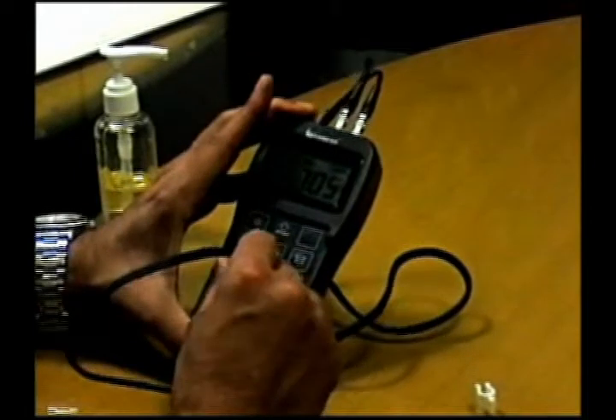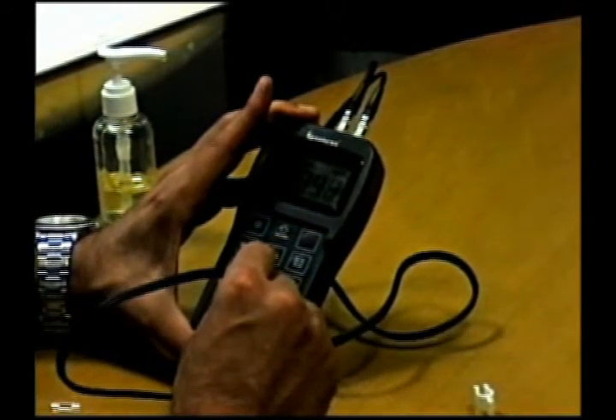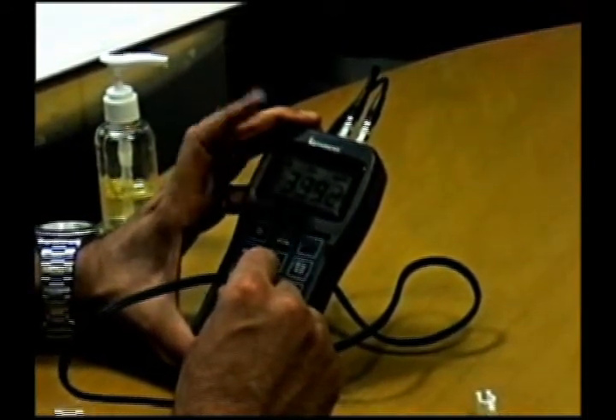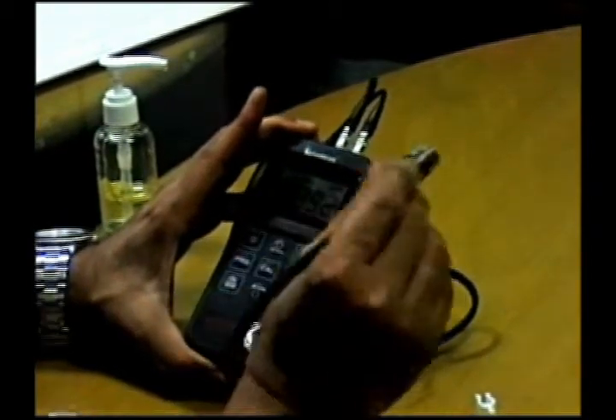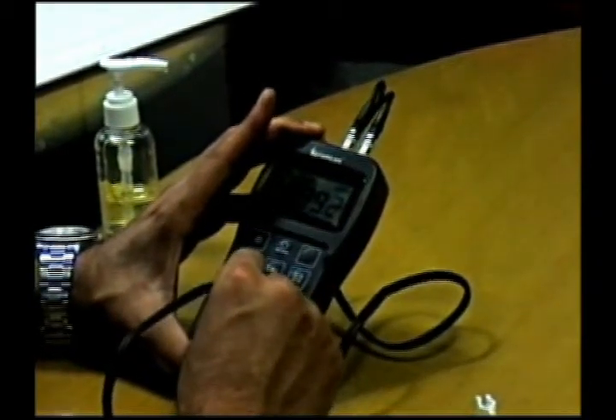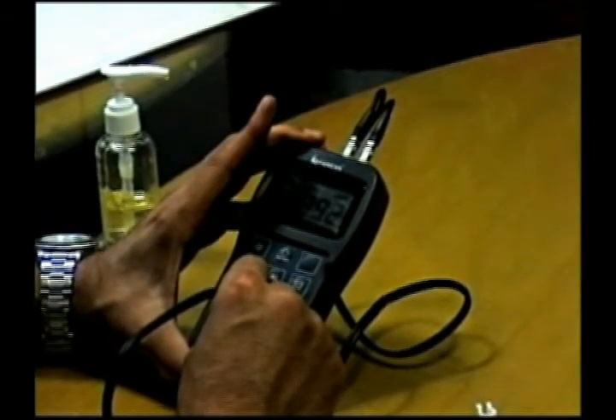This is a probe zero disk, so as soon as we keep the transducer at the top, you have a random value that comes on the instrument, which allows the transducer to be basically calibrated and allows the instrument to be used.